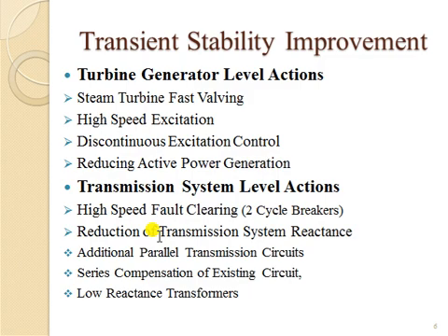Series compensation of existing circuit, this is very important. You are adding some capacitor in series with the line, which will reduce your value of reactance, so that will be XL minus XC, ultimately reducing your overall reactance. But there are some issues like subsynchronous resonance, SSR, which we'll discuss in the next unit on reactive power management.